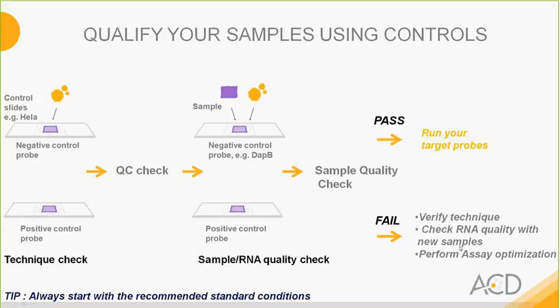Now, this right here is just a reiteration of what I mentioned before, which is your sample qualification, as a visual flow chart. In general, some of our customers may start with step 1, which is using our control cell pellets. If not, our customers may also start here, which is a sample check, running positive and negative control probes on the samples. If it passes, you would move on to running your target probe. If it fails, you would move on to optimization of the assay.